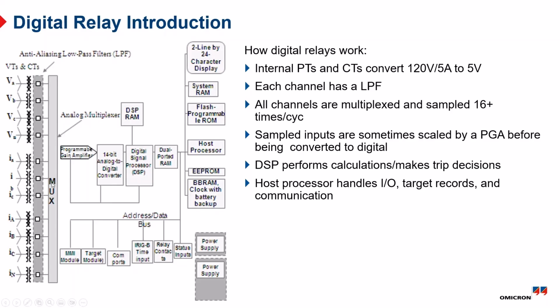The next item in the block diagram here is a multiplexer, and a multiplexer basically serially puts these lines on the programmable gain amplifier and the digital converter. So every time the relay samples, in this particular case, this relay sampled 16 times a cycle. So about every millisecond at 60 hertz, this relay sampled all of the inputs. It would put VA on the line, measure VA, then put VB on the line, measure VB, and so forth. It would measure all of the currents every millisecond. When it puts a line on, the multiplexer puts a line on the amplifier here.